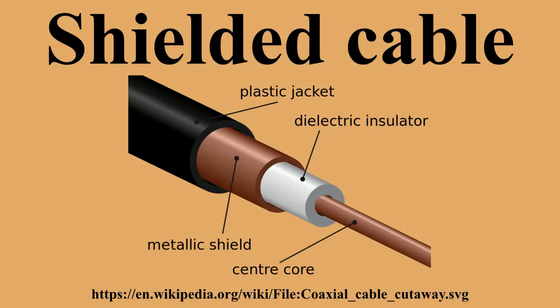IEEE 422 and 525 lists the cable lengths that would limit shield potential to 25 volts for a single point ground application.